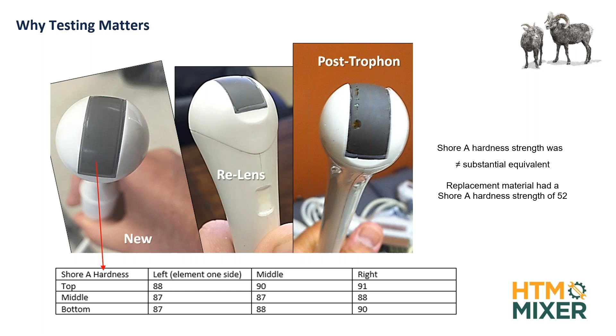They put it in the Trophon, ran what the Trophon op manual said, keep it in there for X amount of time, whatever that time is, and it came out and it had eaten away the lens, and the heated chemical that they used then was saturated into the acoustic stack and killed the probe. So they basically had to buy a probe. When if the lens would have been tested correctly and they'd used the right material, it'd been back up and running.